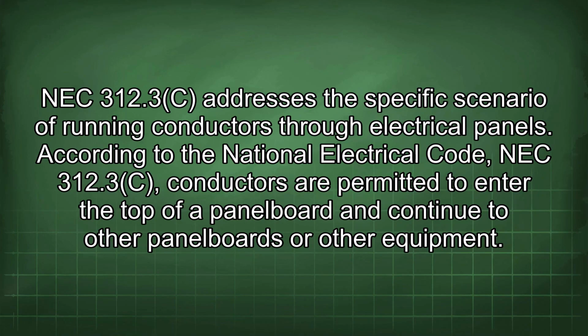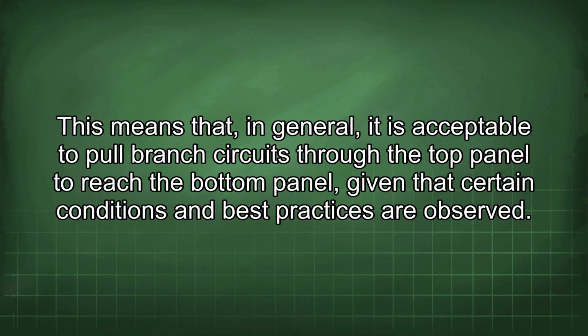NEC 312.3(C) addresses the specific scenario of running conductors through electrical panels. According to the National Electrical Code, NEC 312.3(C), conductors are permitted to enter the top of a panel board and continue to other panel boards or other equipment. This means that, in general, it is acceptable to pull branch circuits through the top panel to reach the bottom panel, given that certain conditions and best practices are observed.